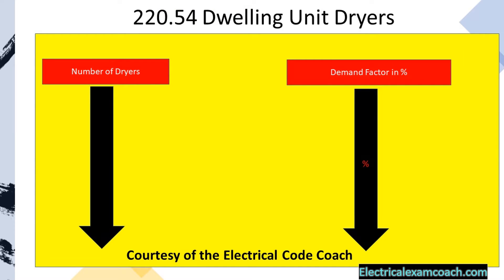When we get to table 220.54, we're always going to read our black bold heading to make sure we're in the right table. We're going to start on the left-hand side and find our number of dryers, then use a straight edge and come over to find our demand factor in percentage. You have to be very careful with these titles — sometimes they're listed as a replacement value and just say 'demand,' and in other tables it'll say 'demand factor in percentage,' which is just a multiplier.